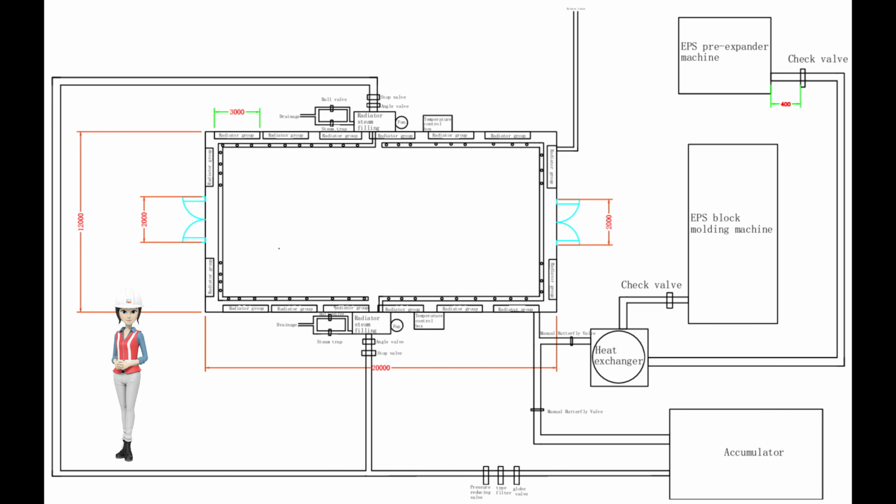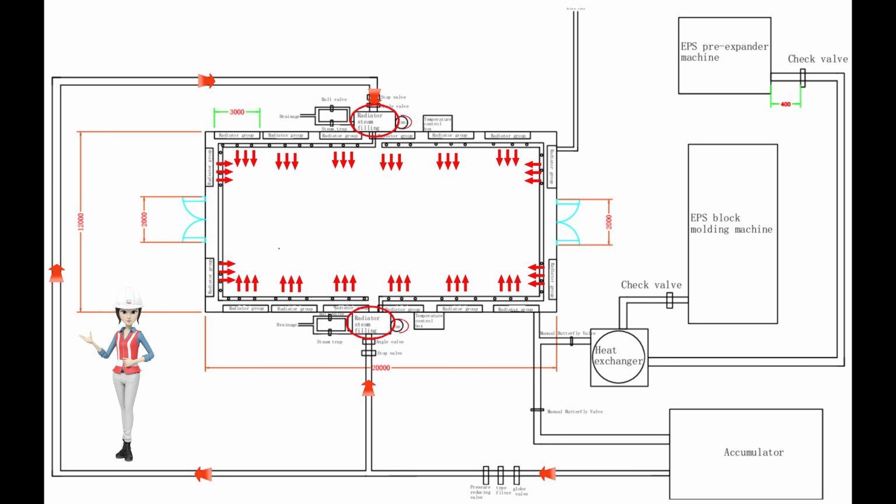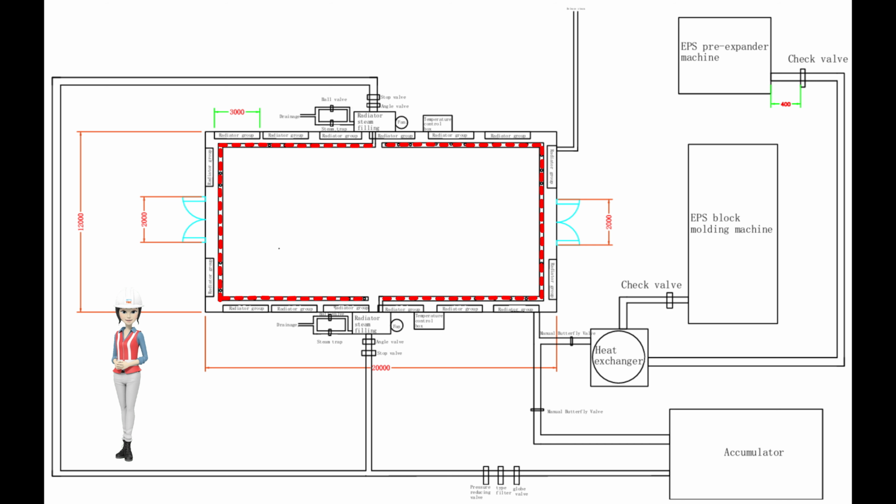2. During working hours, steam from the steam accumulator heats the drying room through radiators and fans, working with perforated metal pipes. This is divided into upper and lower groups. 1. The lower group supplies the right side. 2. The upper group supplies the left side.